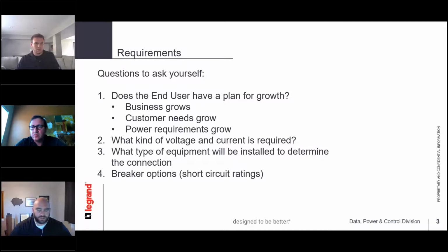It's been interesting with COVID and how the internet itself has changed, where power requirements have grown, where a lot of our customers have ramped up from 30 amp to 60 amp PDUs and made changes in their racks just to utilize the space they have with the additional power capacity they have, with just simply changing out one plug versus any additional power routing, cable routing. Voltage, as Nick spoke, data centers increasingly going 240, 415, copying the overseas for the higher efficiency.